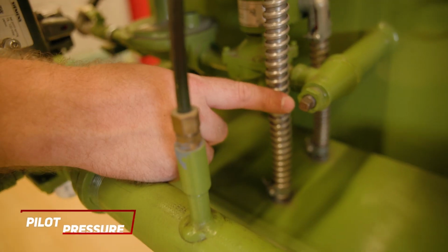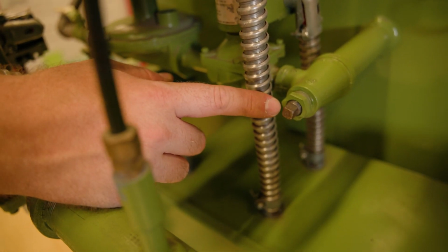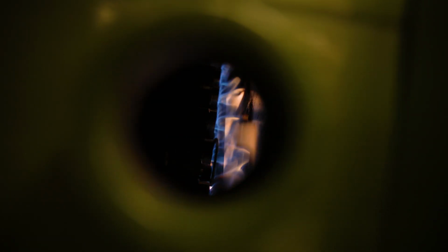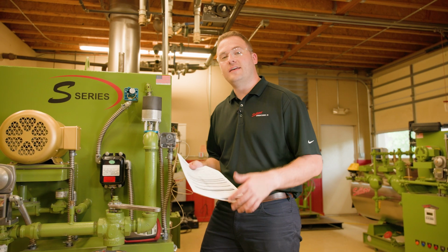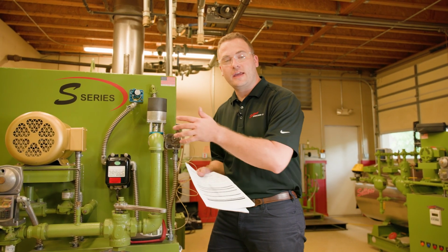The last measurement we want to get is the pilot pressure at high fire. You're going to do that on this tap here. This tap here is a 1/4 inch tap that goes to the pilot line. And that pilot pressure is essential for proper operation of your pilot burners so that they can properly ignite the gas nozzles of your Sellers Manufacturing S-Series boiler. That concludes the process of checking the factory test record against your boiler.